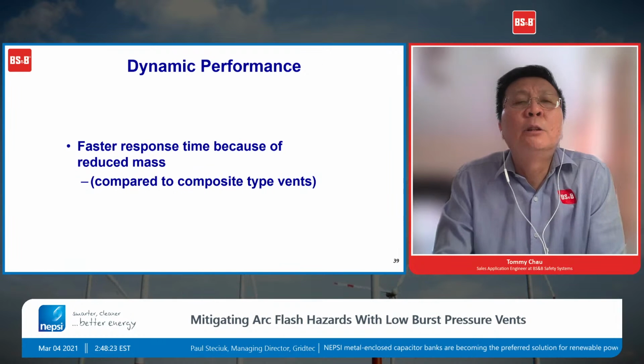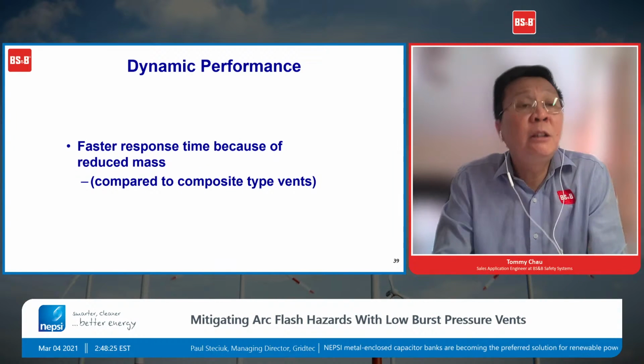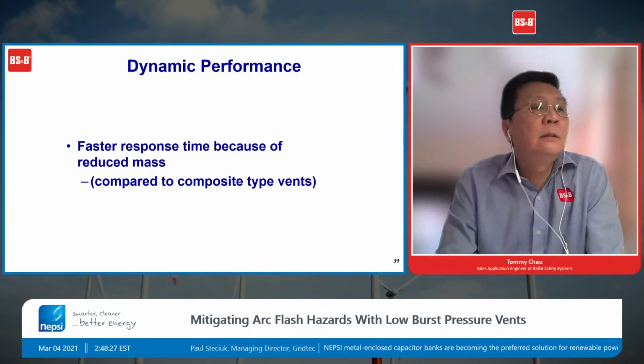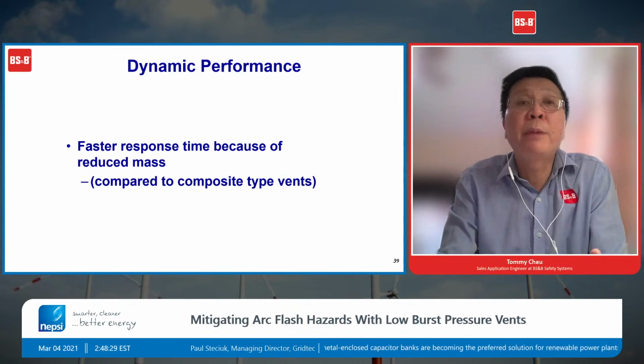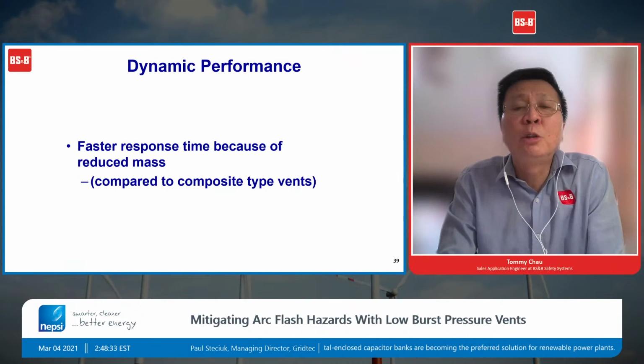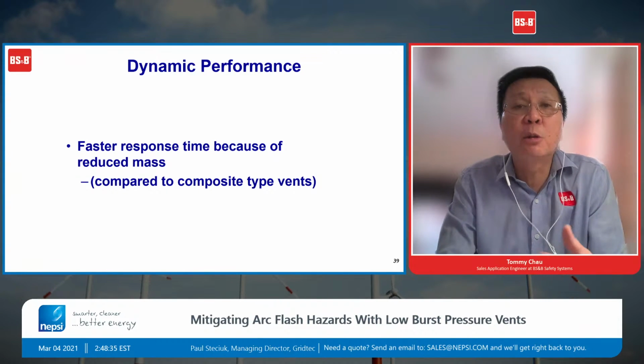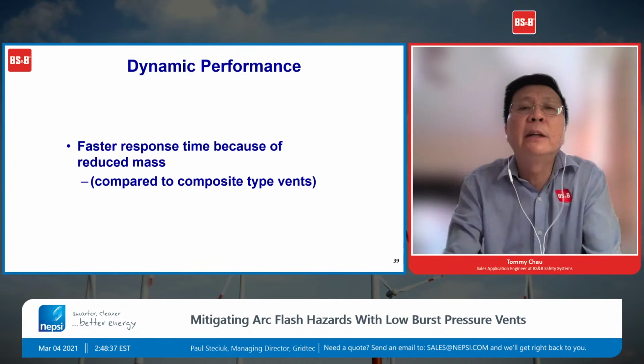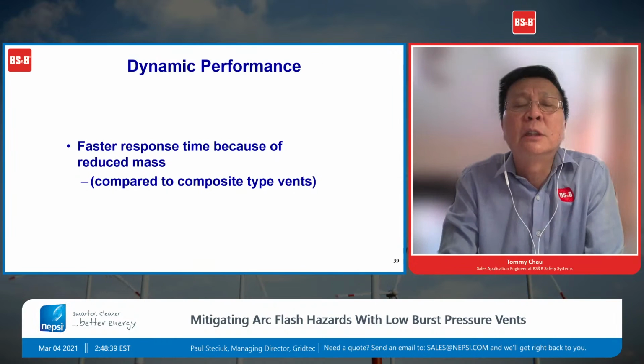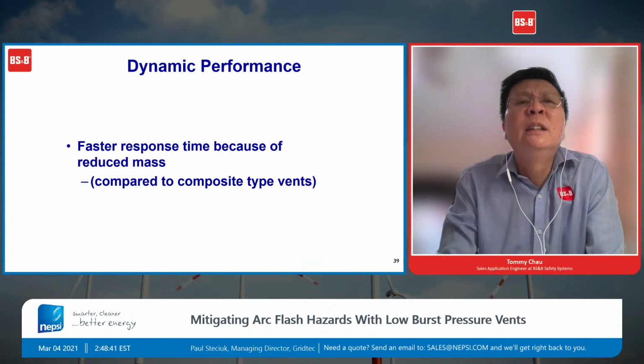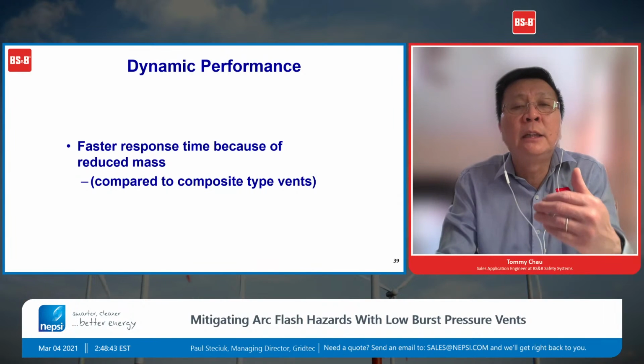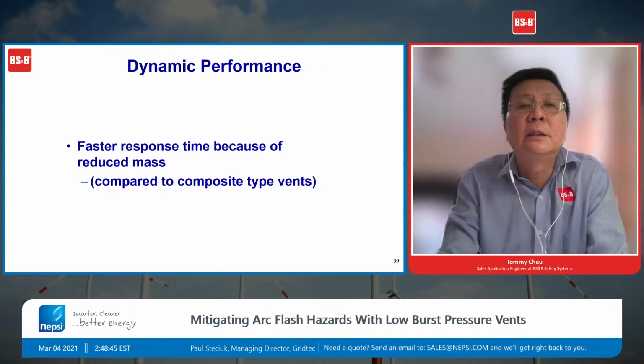So with a single layer material piece of dome panel, the response time is a lot quicker. So you want the explosion vent to open as quickly as possible if you have an event inside your equipment. So the VSP is ideal, and it's very good because it is only a single layer dome construction.